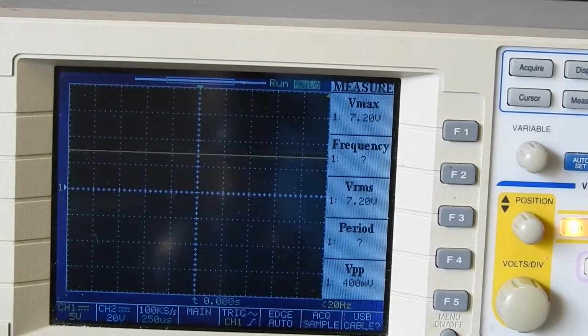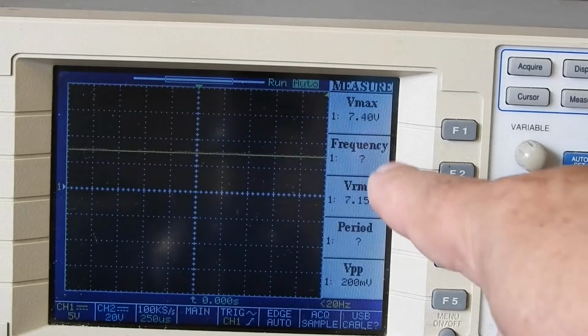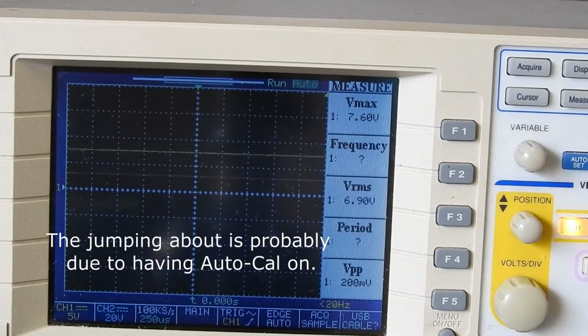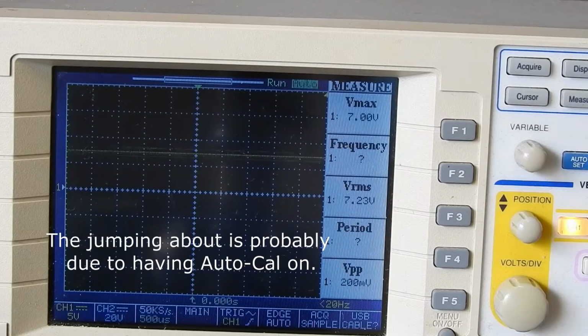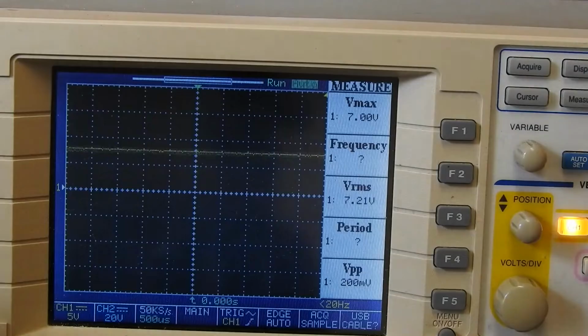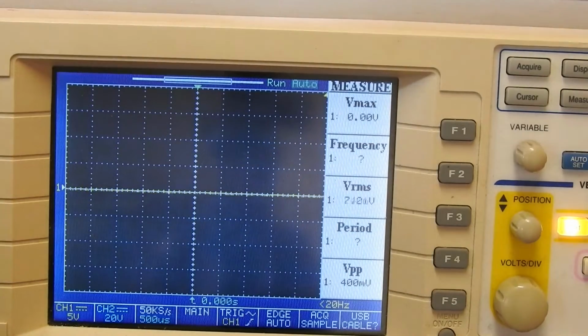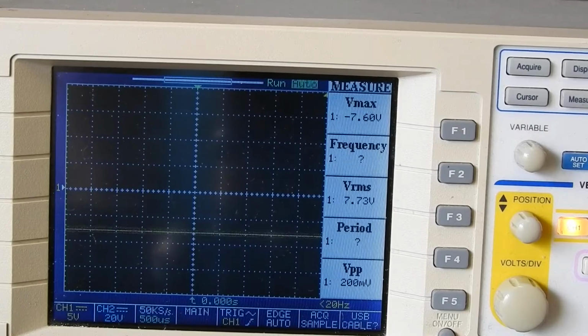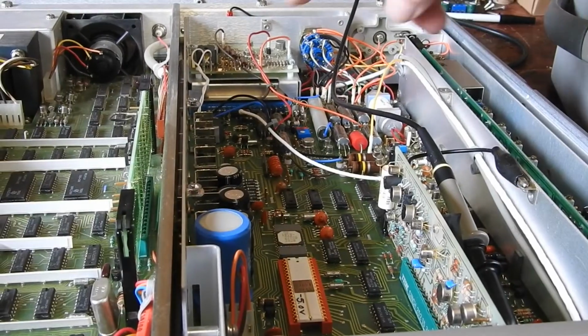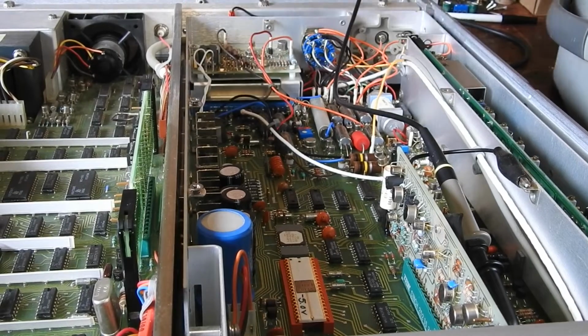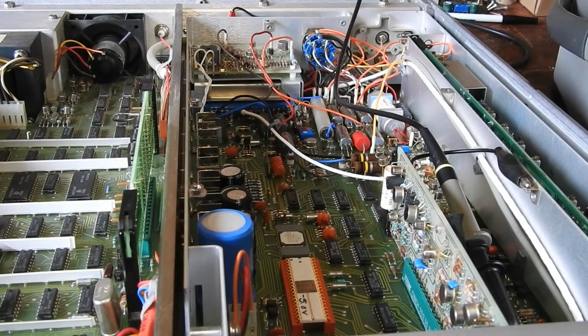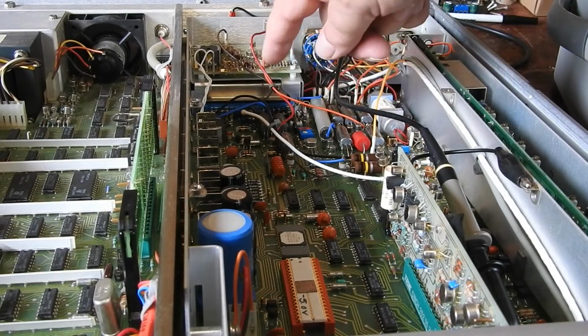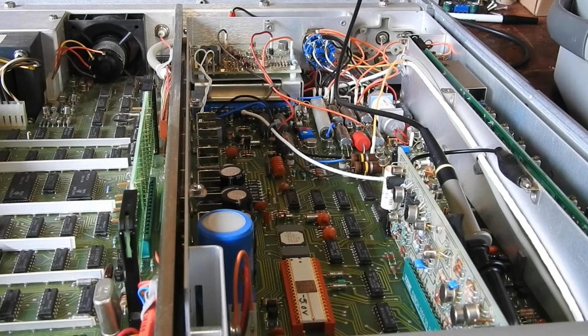Now there's the plus 10. As you can see, it's not steady, and it's 7.4 volts. It's jumping up and down, and the minus 10 is no better. Same thing at minus 10. The reference assembly is down there. It's an unpluggable module. In fact, you can calibrate this thing by unplugging that module, sending it off to get calibrated, and then you just put it back in and the thing's calibrated.